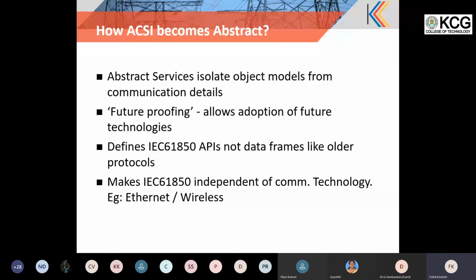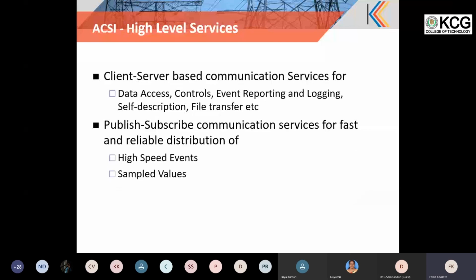Then the higher level services of the abstract communication service interface. There are two models. Client-server model, in which I have mentioned the MMS kind of scenario, station to bay to station communication, that is multiple servers are there, multiple clients can connect. Once the connection is established, it is like a pipe and all the data exchange like data access control, reports, logging, etc. can be achieved. Another scenario is directly over Ethernet, a publish-subscribe kind of scenario. It is used for high speed events like GOOSE exchanged between the devices in a substation, or sampled values, that is from process equipment to the bay. So this is the multicast publish-subscribe scenario.